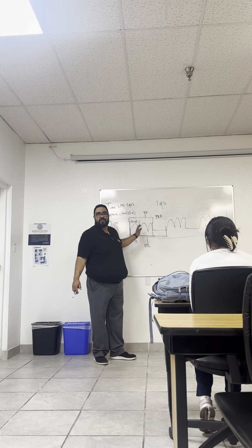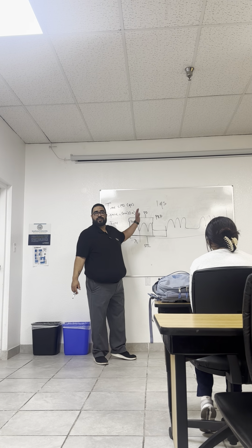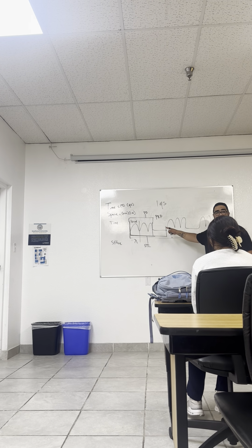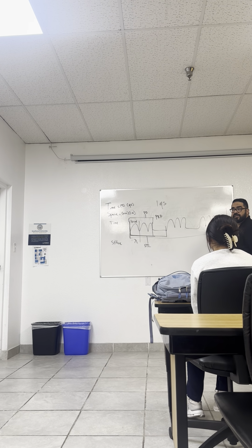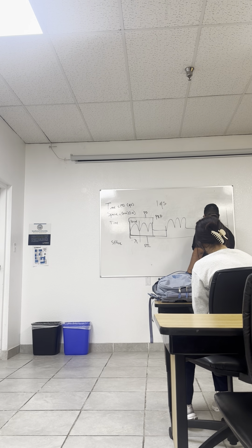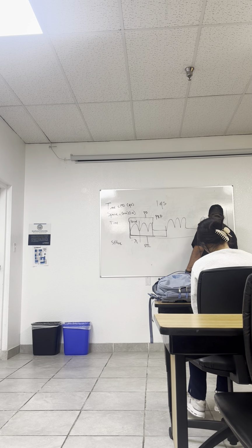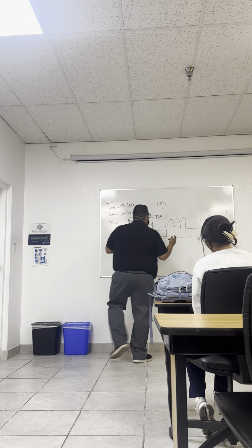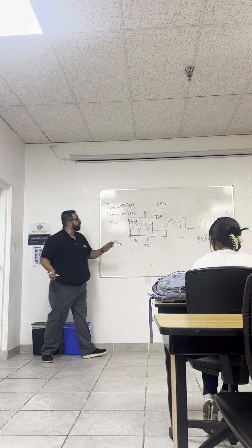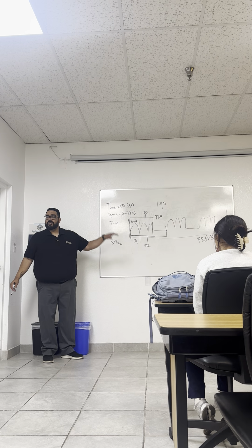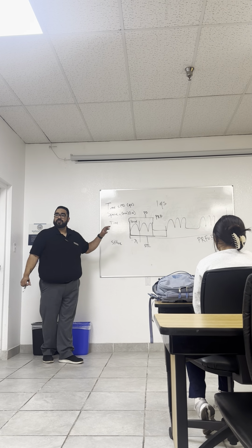So what is that called? Pulse repetition frequency. And in this example, what is our pulse repetition frequency? 3 kilohertz. Our PRF is 3 kilohertz. So we went from the individual cycle to the number of pulses that the transducer is emitting per a given amount of time.